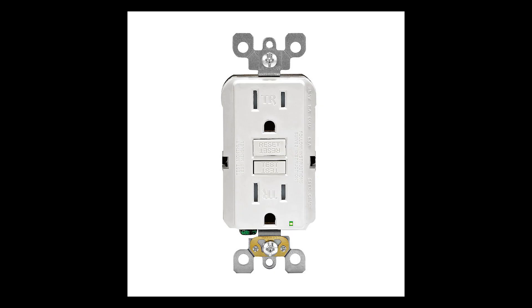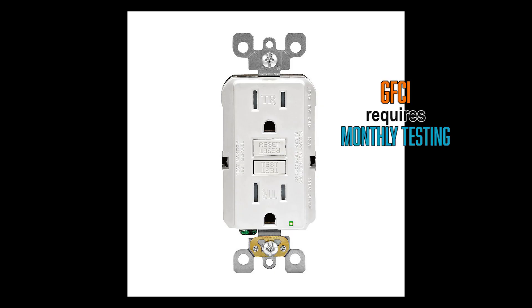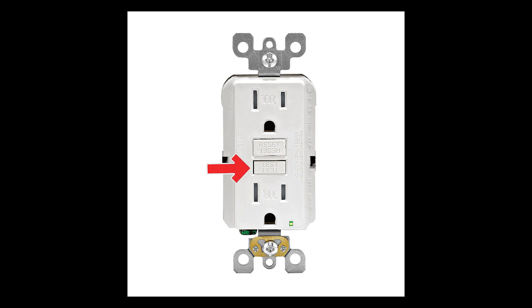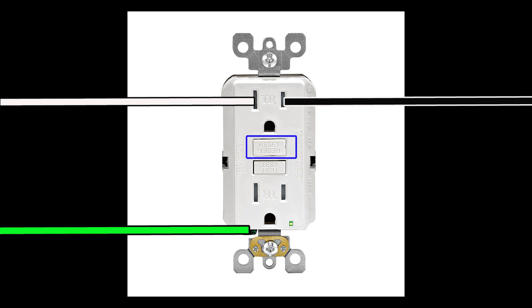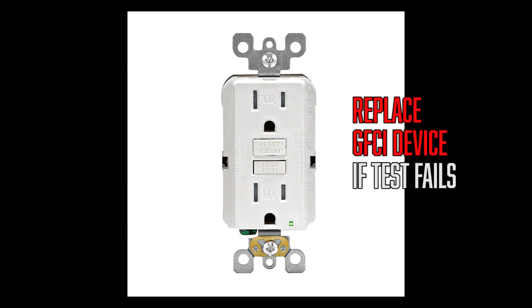A word of caution: GFI outlets and circuit breakers must be tested monthly to make sure that they function properly. Testing is done by pushing the test button. That shuts down the power in the circuit and is supposed to pop the reset button up. By pushing the reset, the power supply is restored. If something didn't act as it's supposed to, you want to replace the faulty GFCI device.